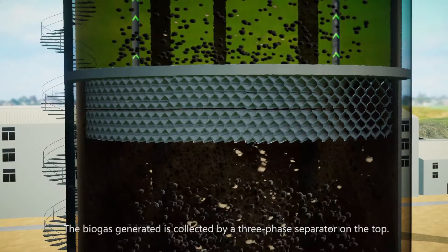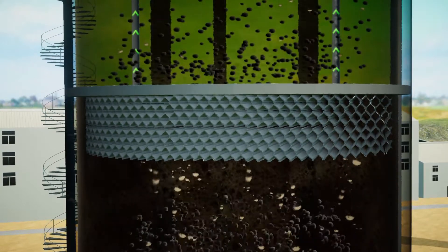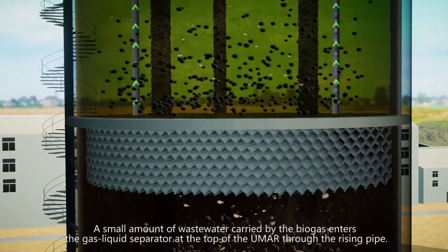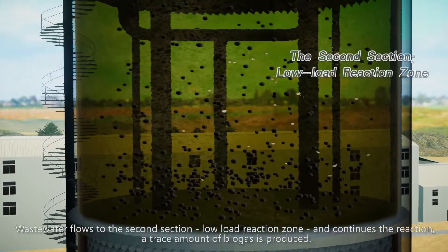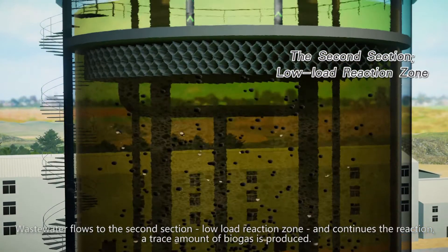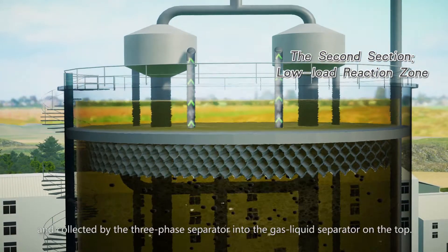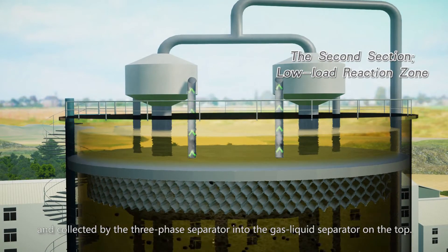The biogas generated is collected by a three-phase separator on the top. A small amount of wastewater carried by the biogas enters the gas-liquid separator at the top of the UMAR through the rising pipe. Wastewater then flows to the second section, the low-load reaction zone, and continues the reaction. A trace amount of biogas is produced and collected by the three-phase separator into the gas-liquid separator on the top.